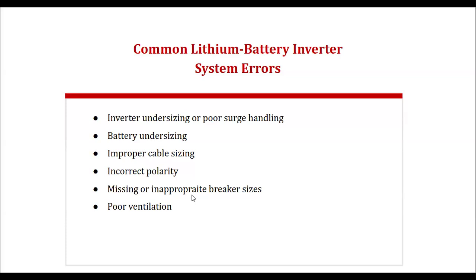Incorrect polarity, the battery will just shut down. You can even damage the battery. You understand? It's not proper to allow incorrect polarity on the inverter. You can damage the inverter itself. Because when you connect positive to where negative is, and then you want to fire the inverter on, or you connect solar and you reverse it, which is not proper, a lot of things will happen.